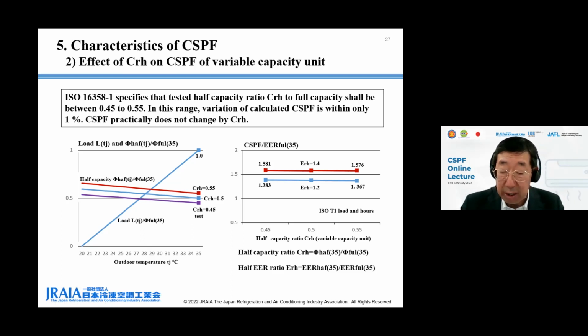Laboratories request the information to set these modes at the time of certification test. The left figure shows load and half capacities divided by 35 degrees C full capacity at each outdoor temperature. The load divided by 35 degrees C full capacity is 1.0 at 35 degrees C. The example half capacities divided by 35 degrees C full capacity are 0.45, 0.5, and 0.55 at 35 degrees C.